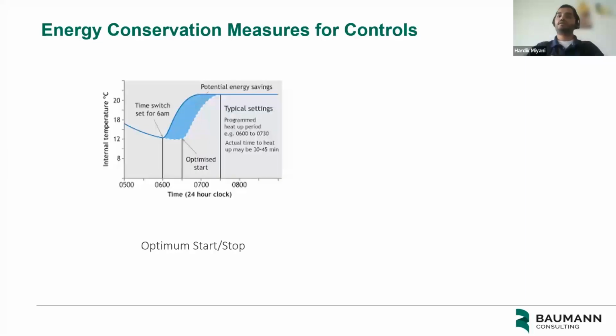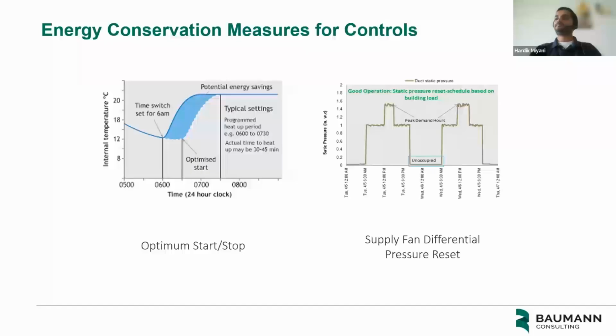Next on the control side is the optimum start stop. Instead of starting the system at a fixed time, be it 5 a.m. or 6 a.m., let the BAS decide the best time to start the system. The BAS will be looking at the building load, like how much is the cooling load or the heating load, and what the ambient temperature is when the building is getting occupied. Depending upon these various factors, the building automation system will decide the best time to start your system and help you to save energy.